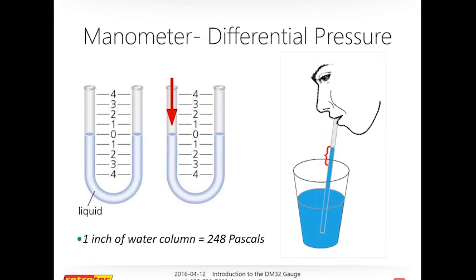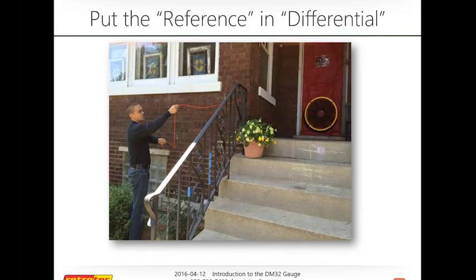Let's talk a little bit about the reference. Here you have me placing a reference tube. Why is that important? Drawing from my experience working at a very busy weatherization company in Chicago, where over two years we did 22,000 retrofits, I saw time and time again a disparity between the test-in blower door numbers, the interim test, and the test-out blower door numbers. What we found when we tried to figure out the difference was that it wasn't the level of expertise—it was often where people put their reference tubing.